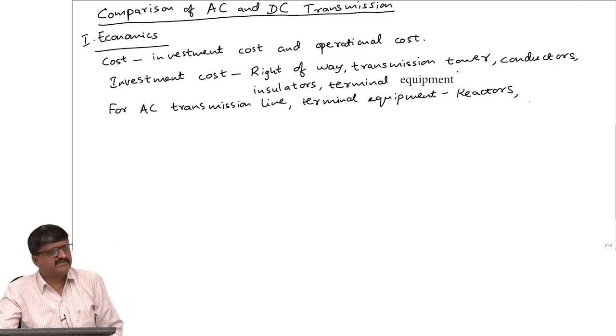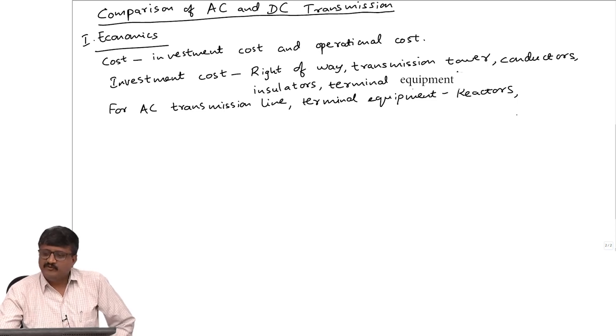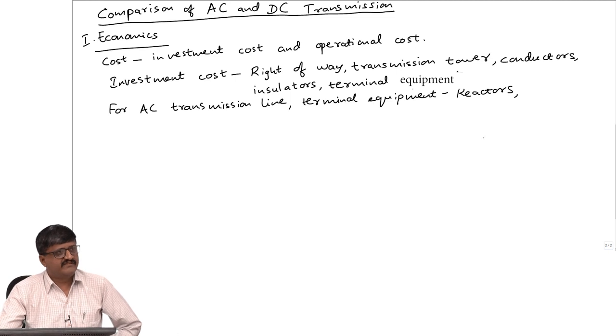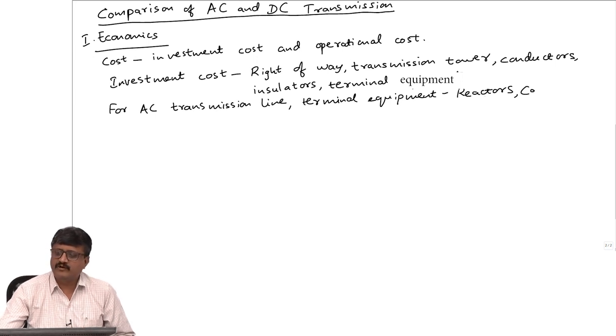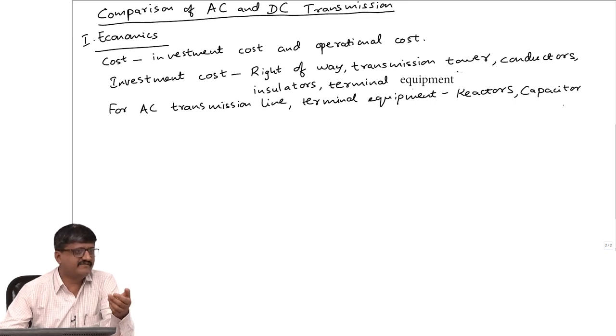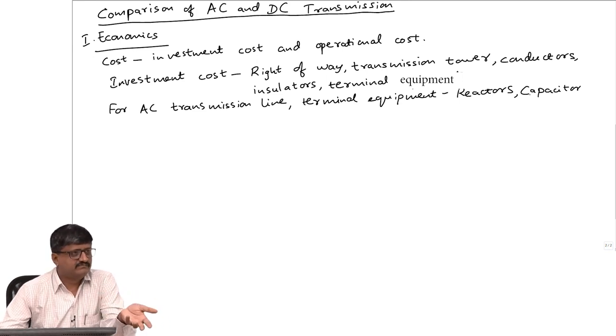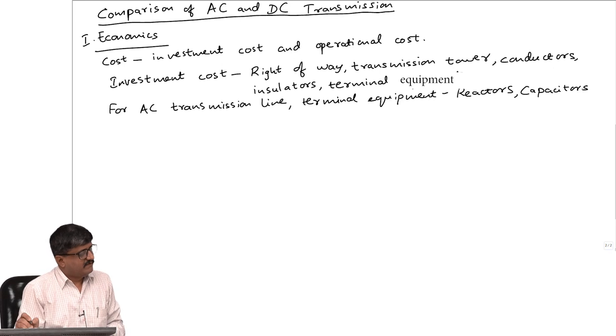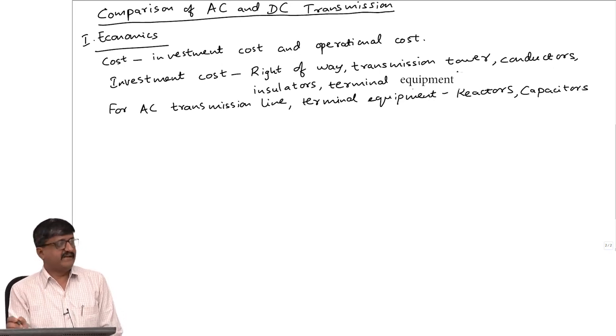You use a reactor to avoid over-voltage, but at the same time when there is heavy load there can be under-voltage. In that case one can put a capacitor. At some point I may connect a reactor; at other times I may remove the reactor and put a capacitor. Putting both simultaneously is counterproductive as one nullifies the other. So these — reactor and capacitor — are the two major terminal equipment for AC.